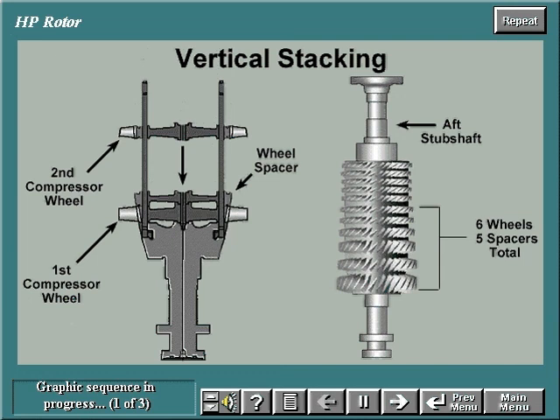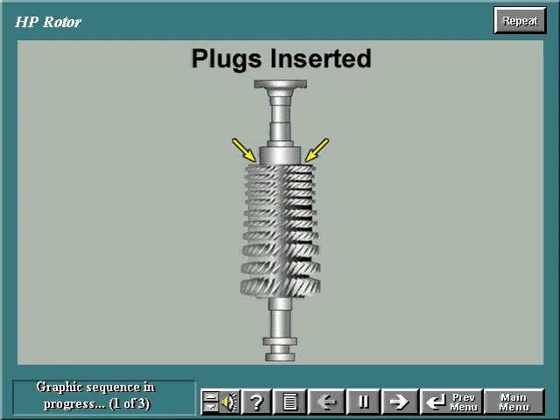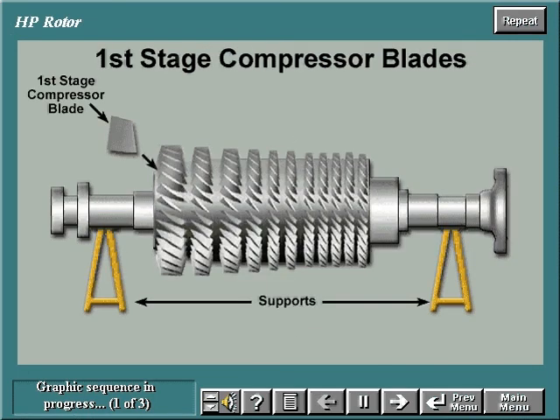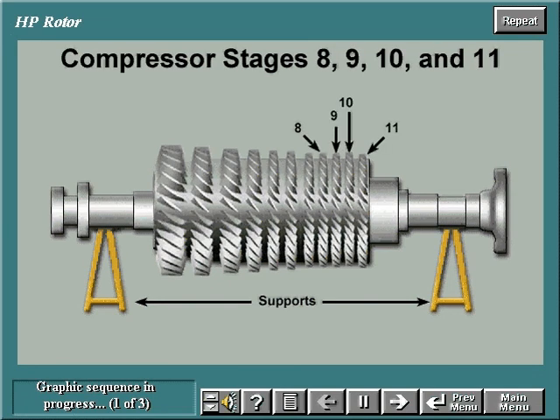Once the last wheel is stacked, the aft stub shaft is slid over the tie bolts and the bolts are tightened. Plugs are inserted in the tie rod slots to prevent particles from entering the slots during turbine operation. The high pressure rotor is then placed into the horizontal position on V-blocks. The first stage compressor blades are inserted into radial slots in the forward stub shaft and staked in position. Compressor blades for stages 8, 9, 10, and 11 are inserted into radial slots in the aft stub shaft and locked in place.